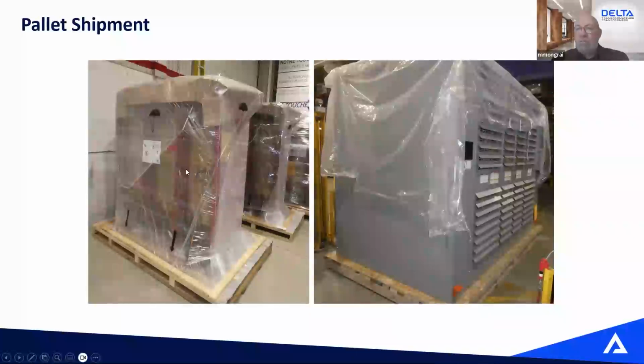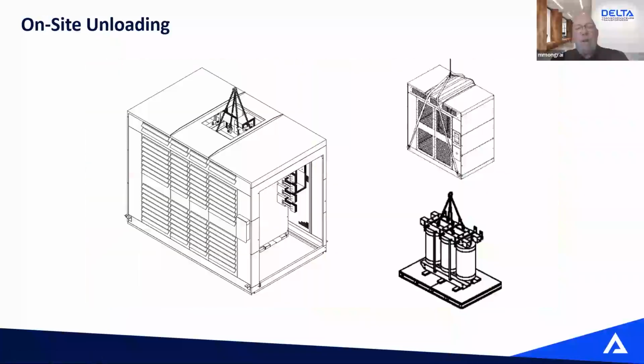The transformer, as you know, is noisy, it vibrates. So all of that vibration, if it's not well controlled and it's transmitted to the enclosure, it just creates an amplifier and makes the transformer more noisy. The second reason is to maneuver the transformer and to unload them. If they're separate components, it's easier. So you can lift everything: the core and coil, the enclosure, and the skid. There's an access hatch on top of the enclosure, so you can unload everything from the truck with the lifting provision on top of the core and coil. And then when the transformer is dropped down either on your loading dock or in the street, you can just lift the enclosure from the skid, and then you can just lift the core and coil from the skid.